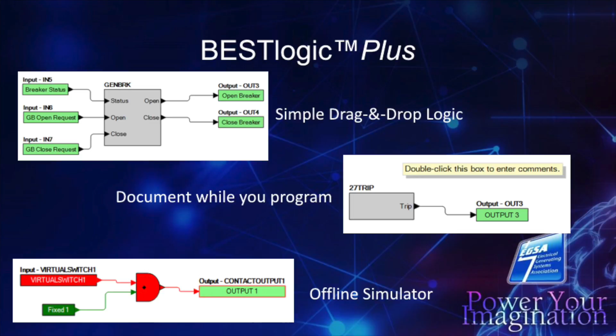We can document the program as we do it, and that allows someone that comes behind myself or one of his technicians to see in the logic why we built the specific part of that logic and what it should be doing. And we can also do an offline simulator, and this really helped on site before we actually push the button to start the generators and close the breakers. We could simulate a lot of this before we actually put any power to any breakers and make sure that everything's going to work. Now with that, I will say, when you're doing a large system like that, as Michael said, we had a lot of things that slowed us down, a lot of things that stopped work.